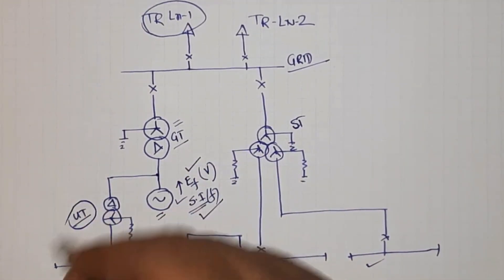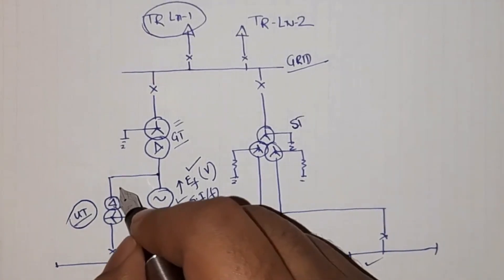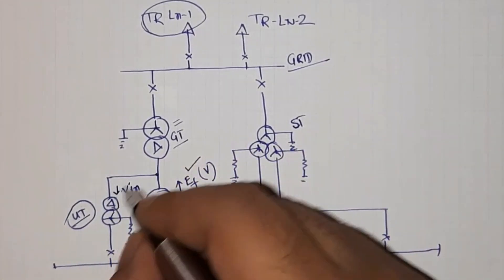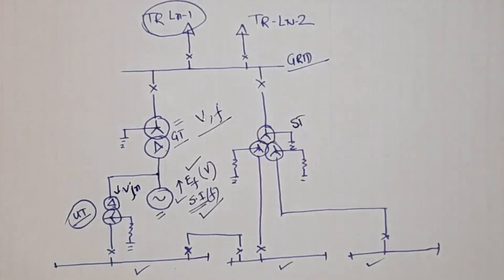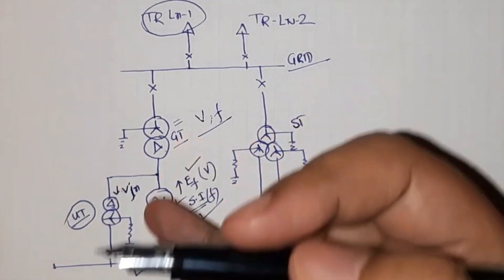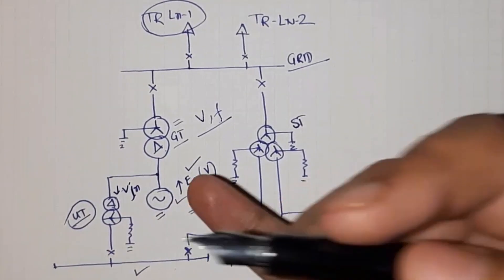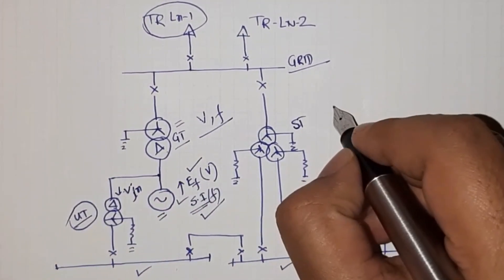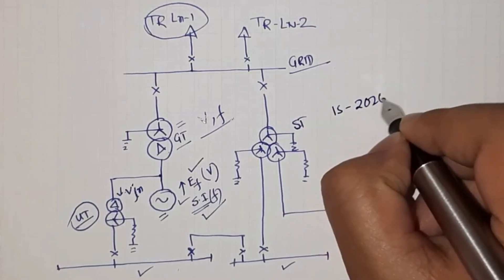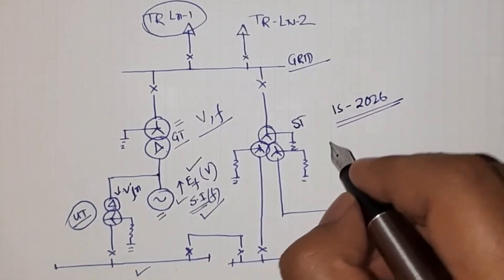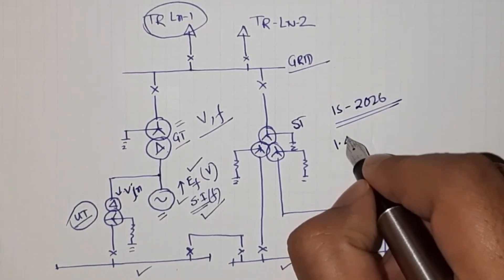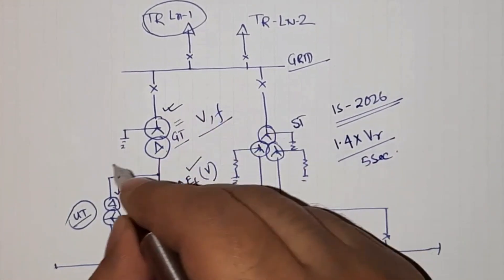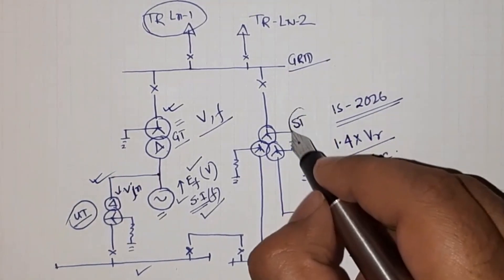The same thing will happen for the unit transformer because it is also connected with the generator — its input voltage will increase. So these two transformers connected directly to the generator will face higher values of voltage and frequency. For that reason, transformers connected directly to the generator have a special characteristic: over-voltage withstand capability. As per Indian Standard IS 2026, these transformers must be capable of withstanding 1.4 times the rated voltage for 5 seconds. This requirement does not apply to the station transformer.